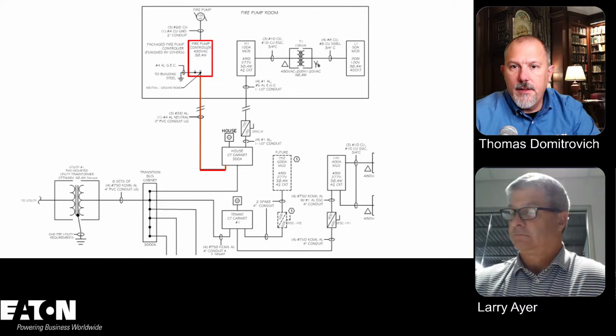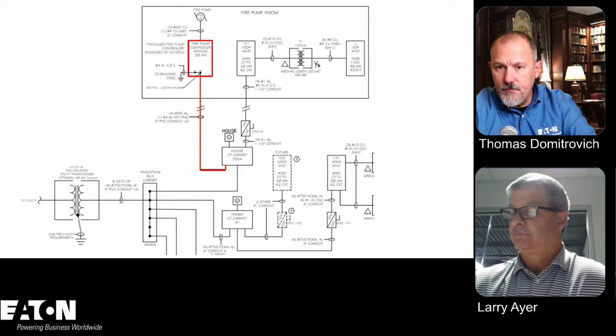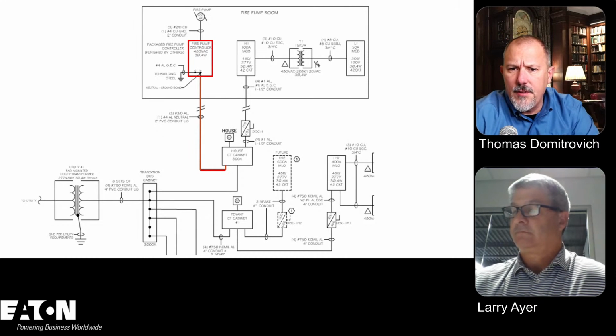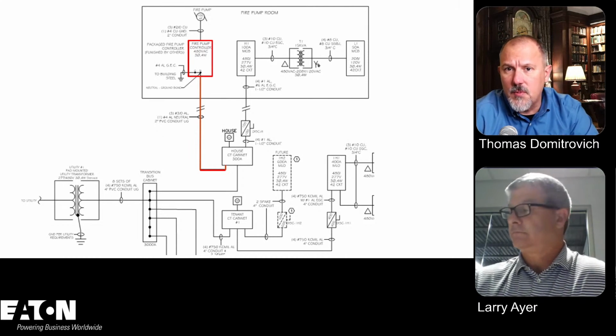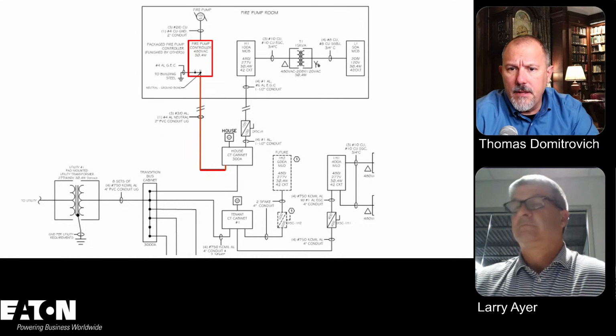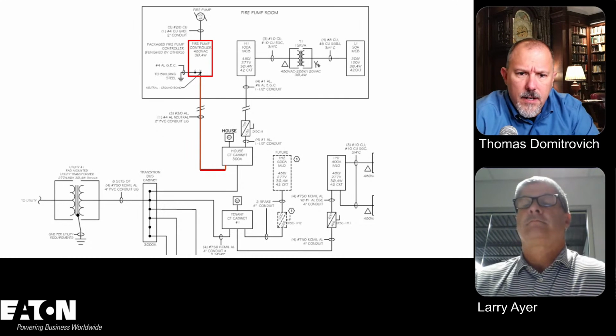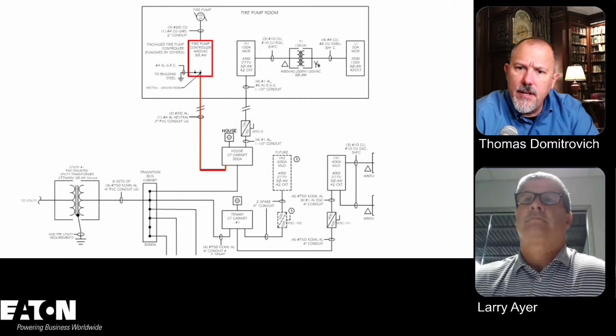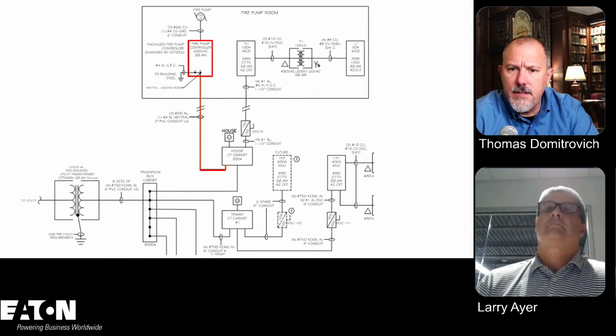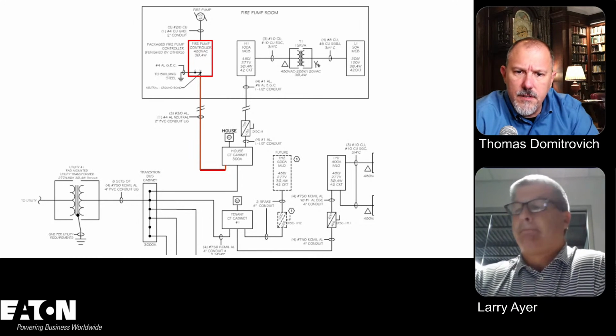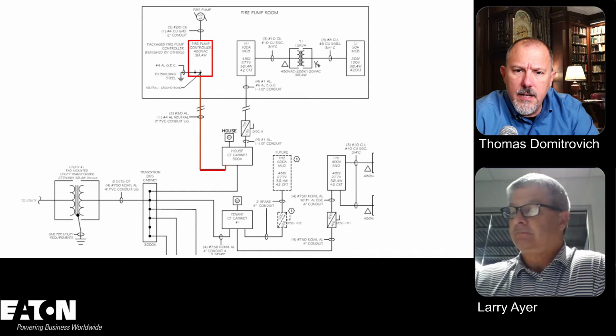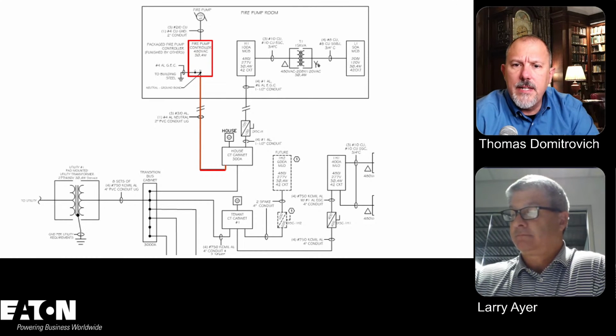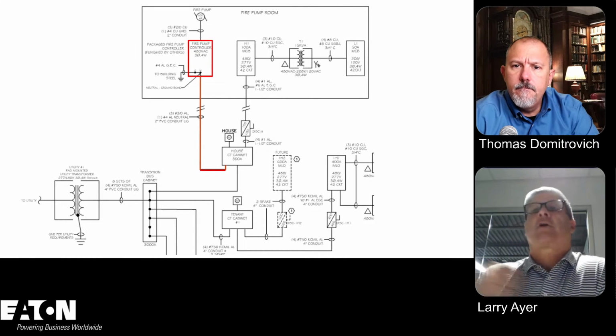And so these are two examples. The one example, in my opinion, looks like a half decent installation, right? There's nothing wrong with this one in that you're coming off of the service, going through that bus cabinet, so there are no overcurrent devices there. You're hitting the CT cabinet, and then you go right down to the fire pump.